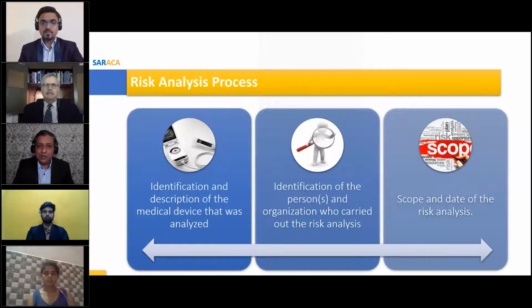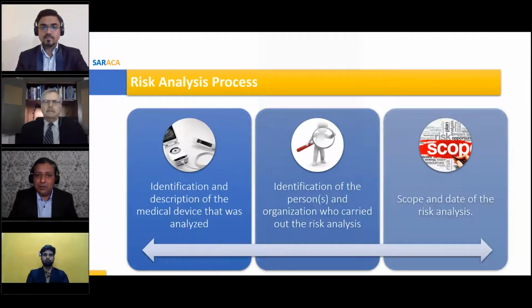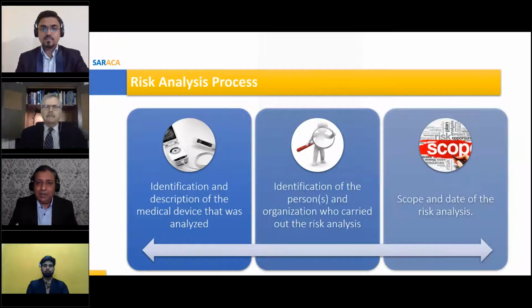And as you know, be it FDA or notified bodies or other regulators around the world, risk analysis becomes very important. Many times I have seen that when you launch your product, you have a certain risk level for a certain cause. Down the line, you are either getting so many complaints on that feature of your product, or you're not getting complaints, but you have forgotten to change your risk. From the last 4 years, it remains the same. And when you compare, your initial assessment of risk has really changed in the last 4 years. You were supposed to go back and change your risk based on the outcome of your product in the market.